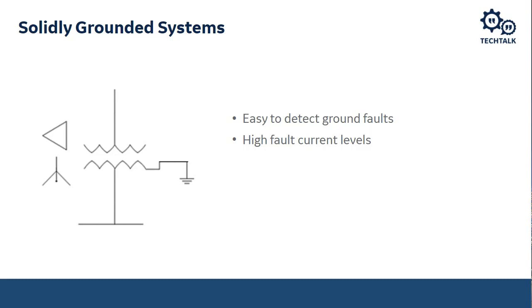However, as mentioned previously, if we allow a ground fault to go phase-to-phase, the same thing applies with a solidly grounded system: since the ground fault currents are high, it can cause permanent damage to the equipment and even collateral damage. And of course, there are safety concerns. Once high ground fault currents start to flow in our system, depending on our ground mat design, we can have safety issues of step voltages and ground potential rise. If somebody steps on two different areas with their left foot and right foot, there could be a potential difference between those two that allows current to flow, and that can cause a safety issue because that personnel has experienced a shock during a ground fault event.